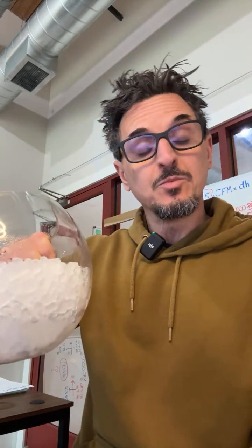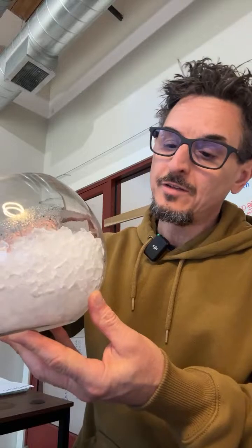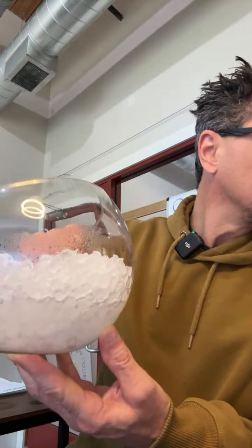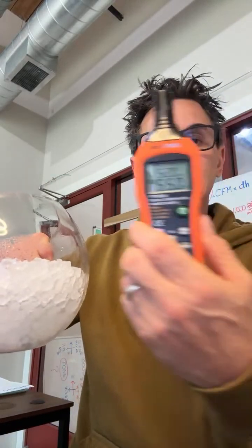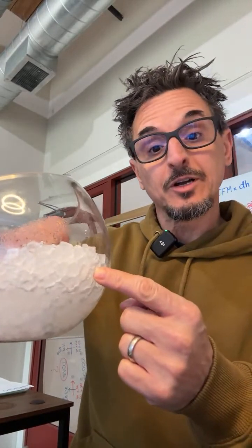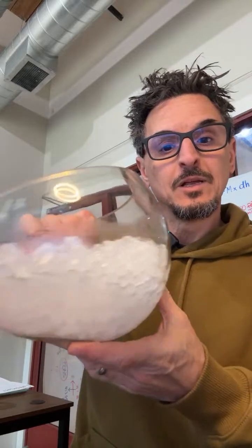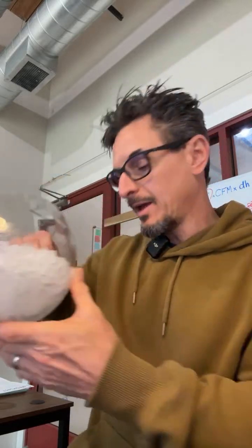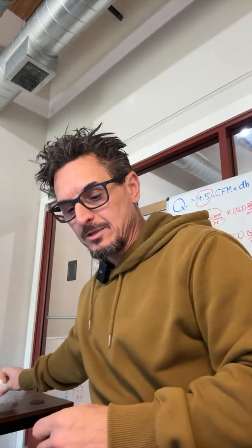So the dew point in here is 55-ish, 57, I think. 55 right now is the dew point. The surface temperature here is 38, so you're condensing water on the surface. Okay? So that's what dew point is. The lower the dew point, the less moisture is in the air. That's how that works. So we'll go through another example of that. We'll look at that in a minute.